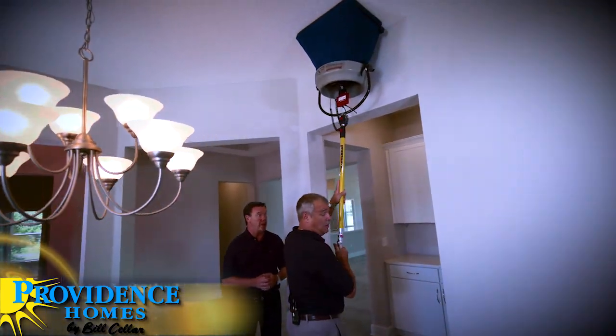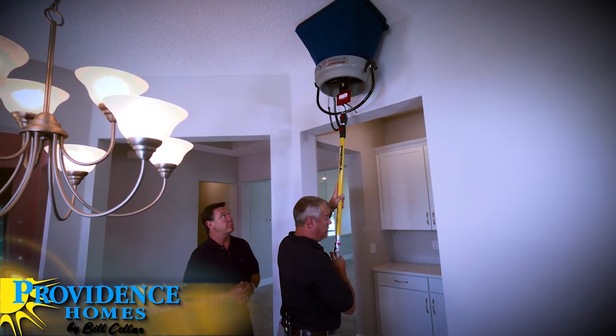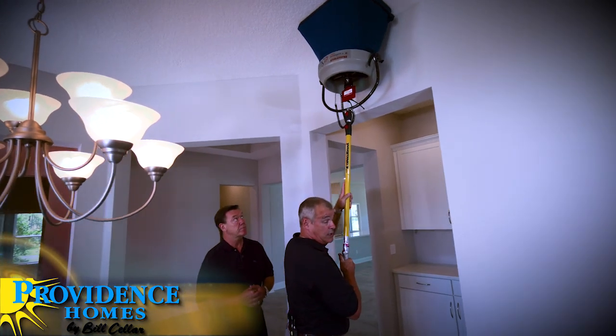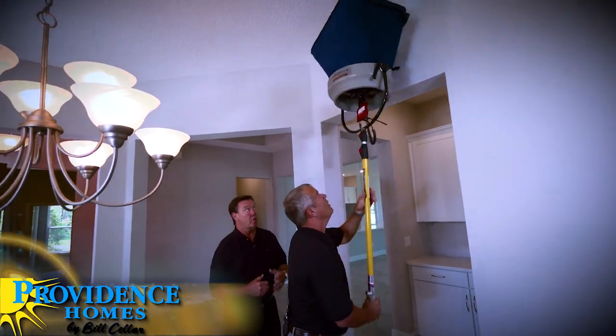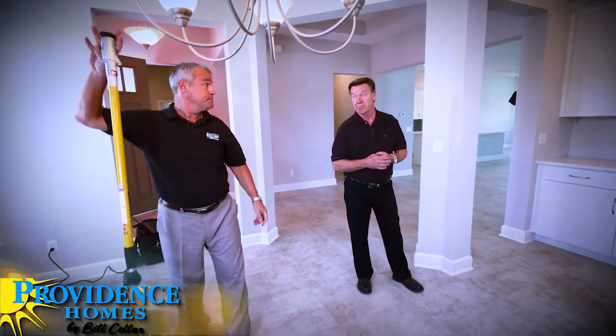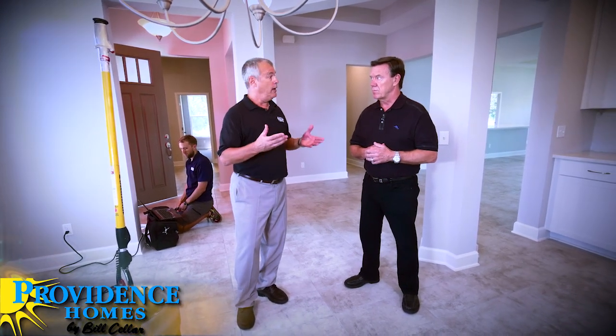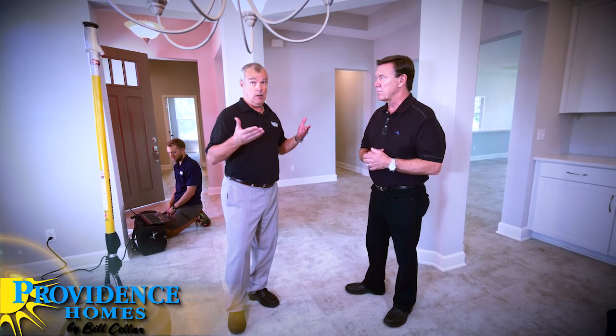We wait about 22 seconds while the sensor captures the airflow, the pressure, and the humidity, and transmits it to the computer, which does the analysis for us — it's actually measuring the airflow coming out of that duct. Once we've captured the airflow out of all the ducts and tabulated it on the computer, we compare it against what the load calculation calls for and make all the necessary adjustments so that the air in every room falls within the tolerance of the load calculation.